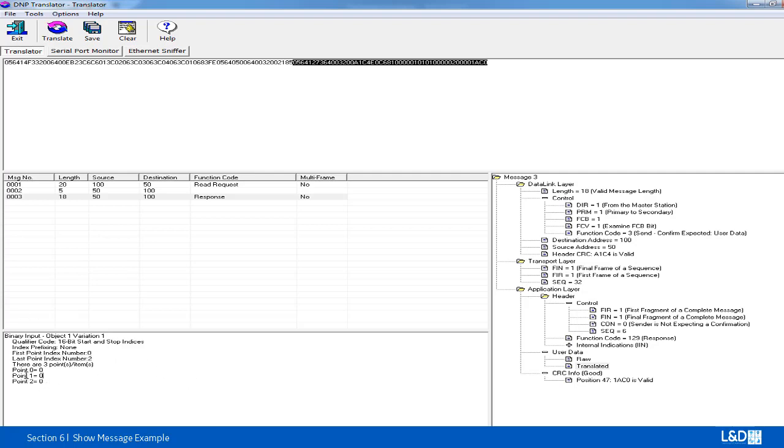One thing to note here: the naming of the points doesn't get transmitted with the message. So you have to make sure that the name or the tag name is what your operator is expecting to see in the point display in both the master and the server device.